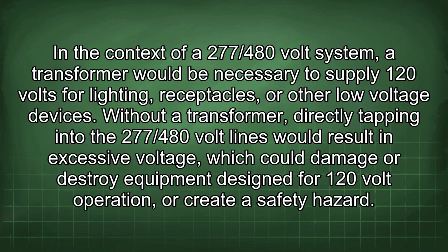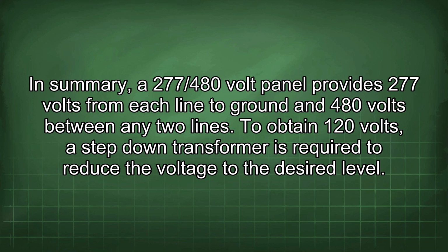In the context of a 277/480 volt system, a transformer would be necessary to supply 120 volts for lighting receptacles or other low voltage devices. Without a transformer, directly tapping into the 277/480 volt lines would result in excessive voltage, which could damage or destroy equipment designed for 120 volt operation, or create a safety hazard. In summary, a 277/480 volt panel provides 277 volts from each line to ground and 480 volts between any two lines. To obtain 120 volts, a step-down transformer is required to reduce the voltage to the desired level.